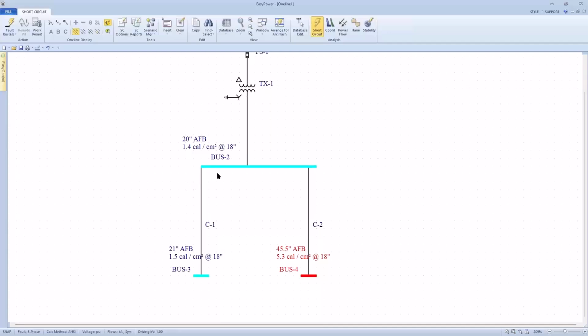Explain. He says, well, right here on the secondary of the transformer, my arc flash boundary is 20 inches. My incident energy is 1.4 calories per square centimeter. So I know I can work safely on this bus with a 4-calorie PPE. If I walk 50 feet away to this bus, the arc flash boundary is 21 inches. My incident energy is 1.5 calories per square centimeter at a working distance of 18 inches. So I know I can work safely on this bus with a 4-calorie PPE.